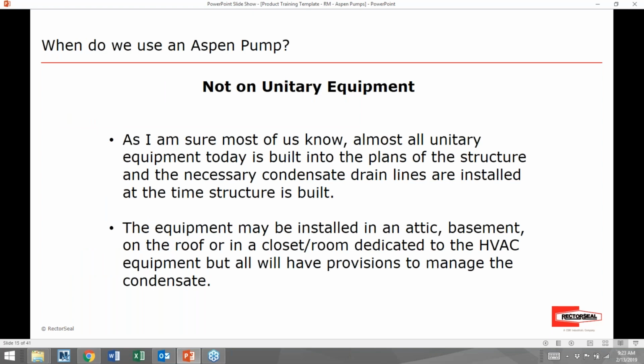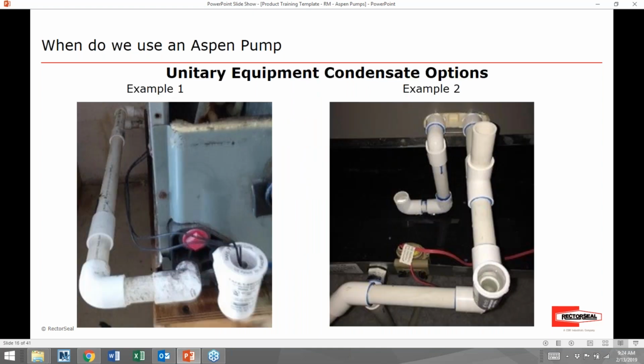So speaking of product applications, when exactly do we use an Aspen pump? Well, your first answer is not on unitary equipment. As most of you should be aware, almost all unitary equipment today is built into the plans of the structure at the time the structure is being built. And all the necessary condensate drain lines are installed well before that structure is completed. The equipment for unitary might be installed in an attic or a basement, some kind of room or closet, the roof, or someplace dedicated for HVAC equipment. But any of those applications will have a provision to manage the condensate. Here's a couple of examples of a typical unitary condensate option.